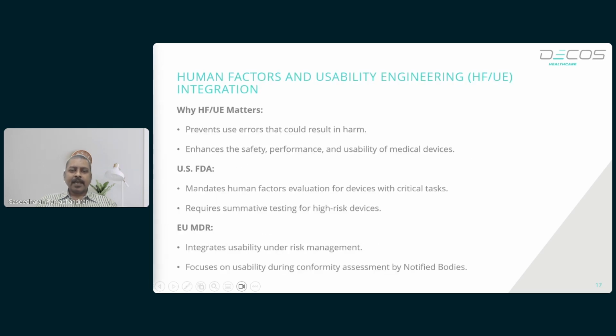Both US FDA and EU MDR emphasize incorporating HF/UE principles early in the design process. Human factors focus on the interaction between humans and devices to minimize user errors and to ensure device safety and effectiveness. The FDA emphasizes human factors in pre-market submissions, particularly for high-risk devices.